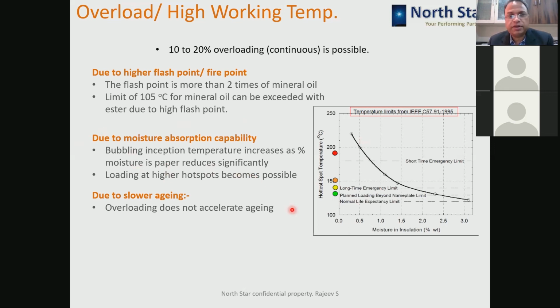The bubbling is a phenomenon where the moisture in the solid insulation gets released at higher temperatures in the form of bubbles. And as the bubbles are released, these bubbles travel to the Buchholz relay and the transformer trips. So when the moisture is higher, the bubbling starts at a lower temperature, meaning at a lower load. So you cannot load the transformer to higher values if the moisture in the transformer is high.